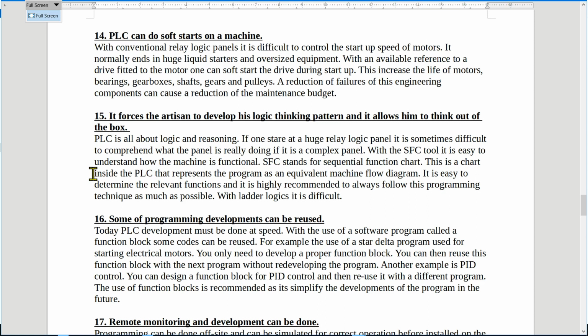And in my life, I have met people that refuse to use any laptop to help them with fault finding. In their minds, they have an SFC diagram actually drafted, and they know exactly what will happen if that input is made and that input is made, then this will happen, and they understand the machine. And even without the aid of a laptop programmer, they can actually find a fault on the machine. Now, it's easy with SFC to determine the relevant function, and it's highly recommended to always follow this programming technique as much as possible.